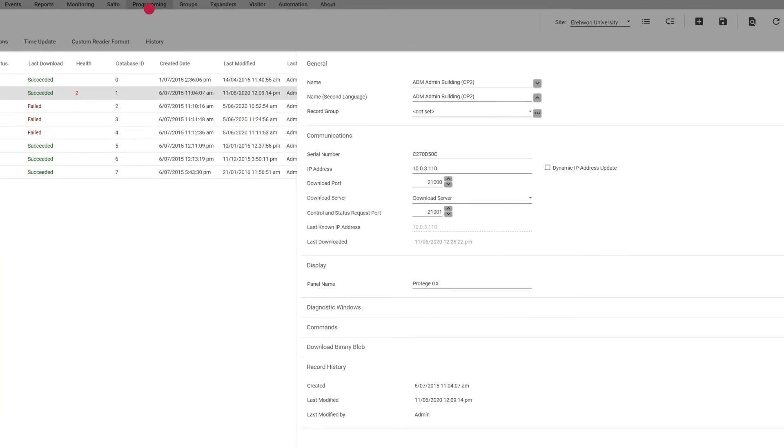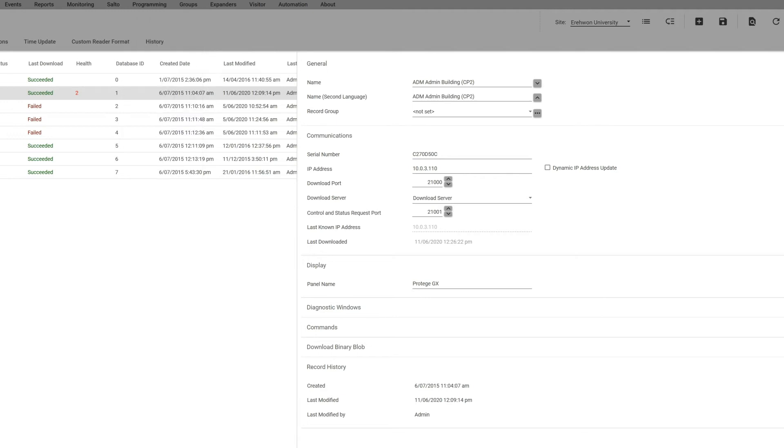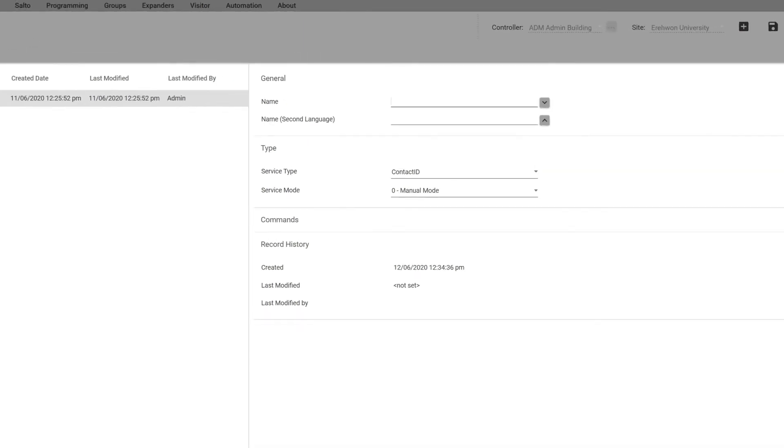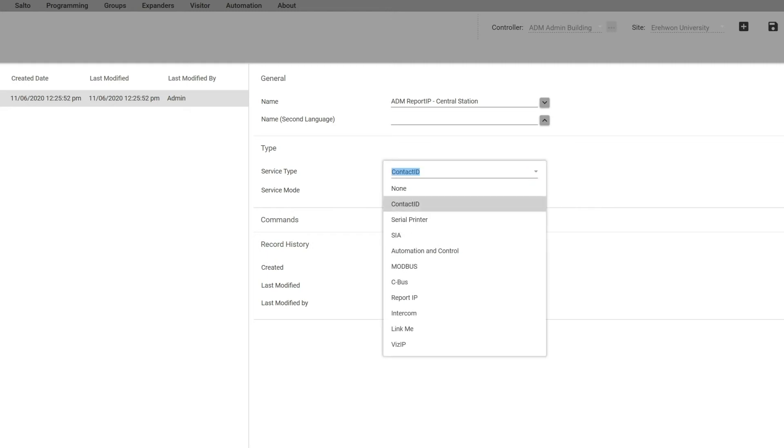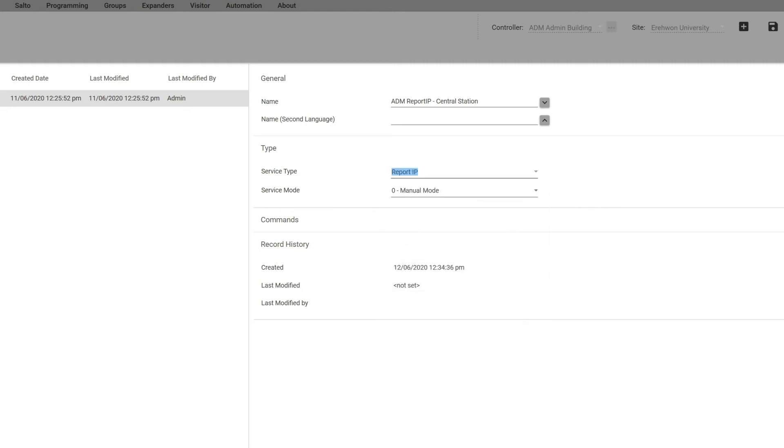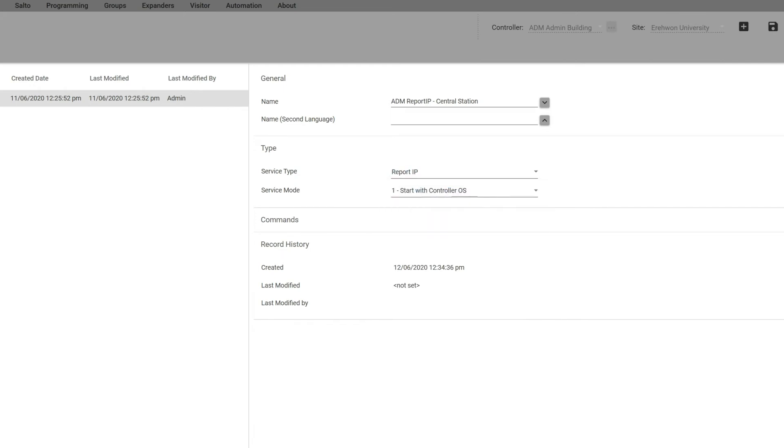We go to Programming and instead of phone numbers, because you don't need a phone number because it's going through your IP, you're going to just go to Services and you're going to add, and maybe I'll call that Report IP and what central station it is. Then make sure that you pick the correct service type. It defaults to Contact ID, you want to change that to Report IP. And again, I want to start the service if the controller goes back down and comes back online again, so I'm going to choose one.